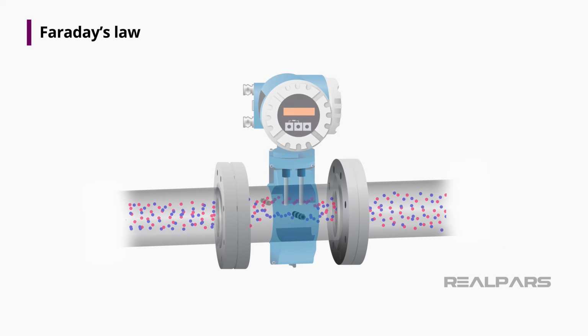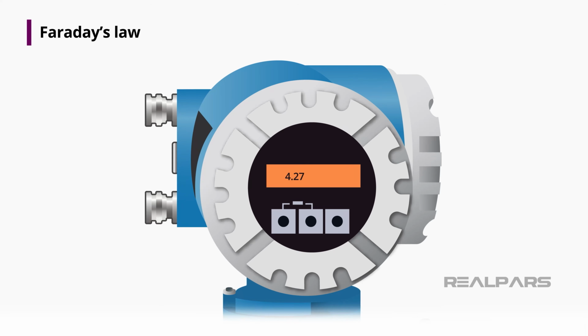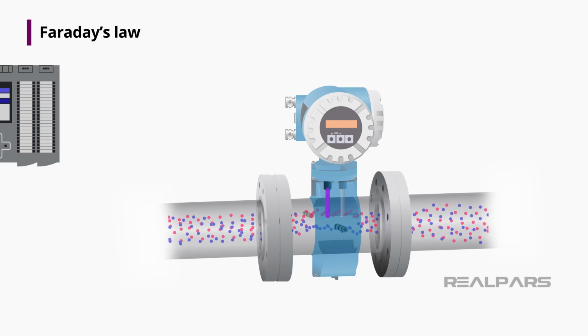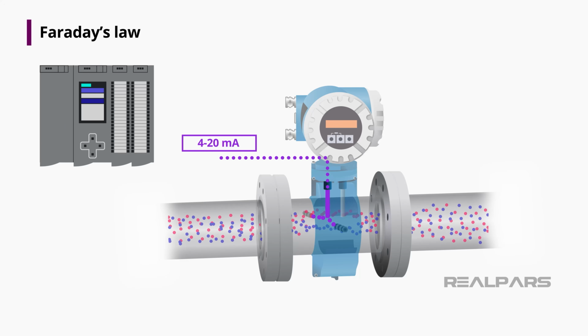The generated EMF, or electrical potential, or voltage, is sensed by two leads, or electrodes, which are connected to the mag meter's transmitter. The transmitter translates the strength of this electrical signal into a volumetric flow rate, and sets the transmitter's 4 to 20 milliamp output to provide an analog signal to the control system.